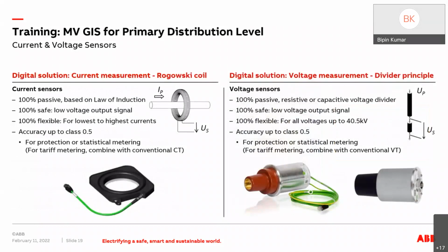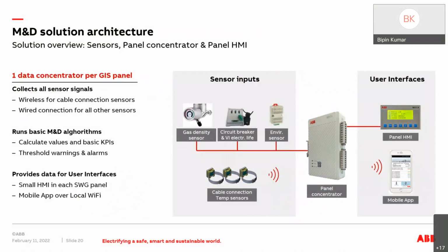What we have done here is a current sensor based on the Rogowski coil principle, and a voltage sensor based on the RVD, that is resistive voltage divider, principle. Now with these sensors in place, they can very well work as the conventional current and voltage transformers. And we have also done a sort of saving analysis to give a commercial nature to it. So we have compared a similar 14 panel board using sensors and a 14 panel board using conventional current and voltage transformers. Over 30 years of lifetime, they end up saving approximately 15 to 20 lakhs for a customer for only a 14 panel board, because they practically do not have any windings, so they do not have any energy loss aspect to it.